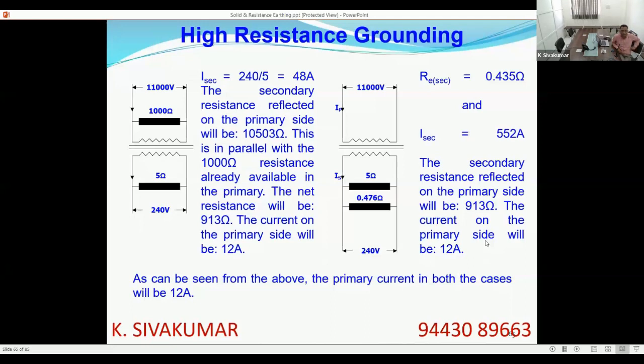Now, take the 5 ohm resistance of the LV, multiplied by the square of the transformation ratio. Transformation ratio is 11,000 by 240, whatever it is. You square it and multiply by the 5 ohm. It will appear as a very high resistance, 10,503 ohms. The 5 ohm resistance you have connected on the 240 volt side, when you multiply by the turns ratio square, will appear as 10,503 ohms on the 11 kV side. Now, there is already a 1000 ohm resistance in parallel. For the net resistance of parallel resistances, R1 R2 by R1 plus R2, the effective resistance will be 913 ohms. When you connect 913 ohms on the HT side, the current will be 11,000 by 913, somewhere around 12 ampere.